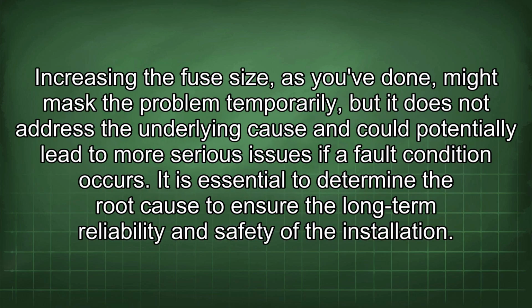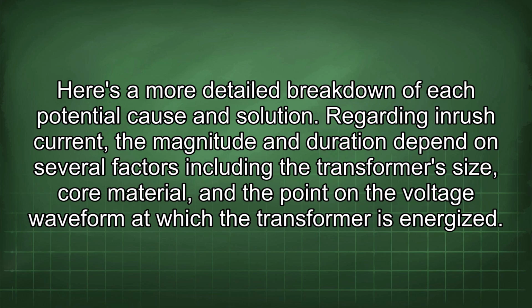Increasing the fuse size, as you've done, might mask the problem temporarily, but it does not address the underlying cause and could potentially lead to more serious issues if a fault condition occurs. It is essential to determine the root cause to ensure the long-term reliability and safety of the installation. Here's a more detailed breakdown of each potential cause and solution.